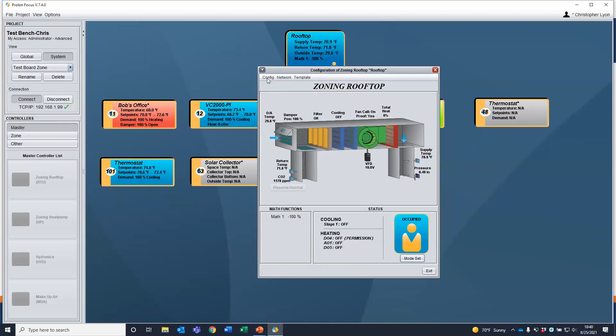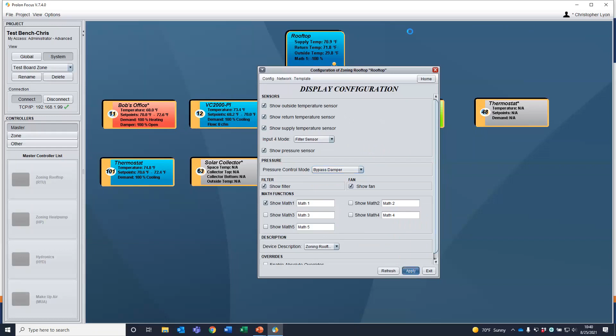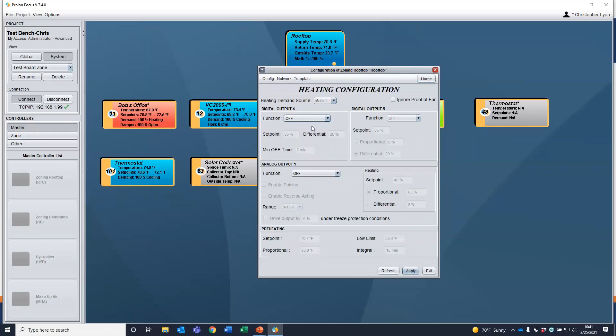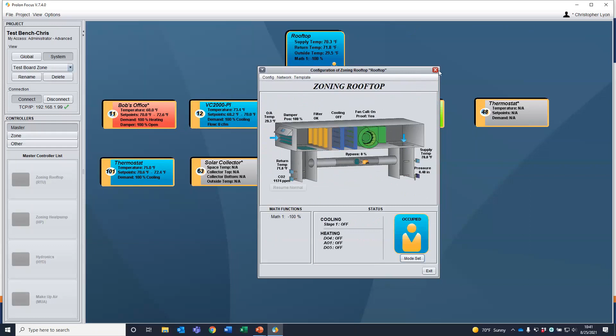Maybe we don't have a VFD controlling the speed of our fan. It's real easy to change this, maybe it's a bypass damper instead. We hit apply, and then guess what, that graphic is all good to go, it automatically changes. And I'll show you that with heating too. If I turn off all of my possible heating output, so everything is off here now, have a look at what happens. It's gone. The graphics adapted right there.